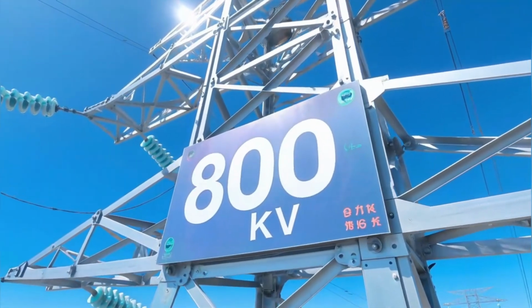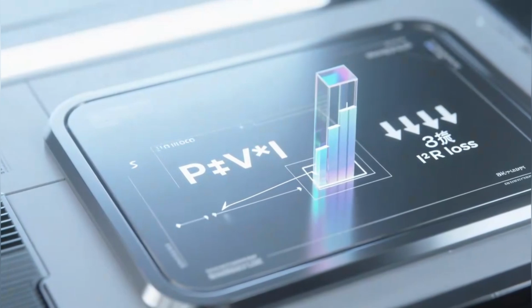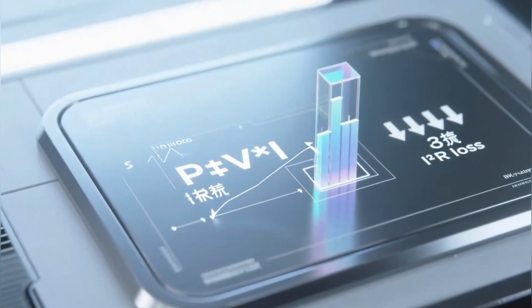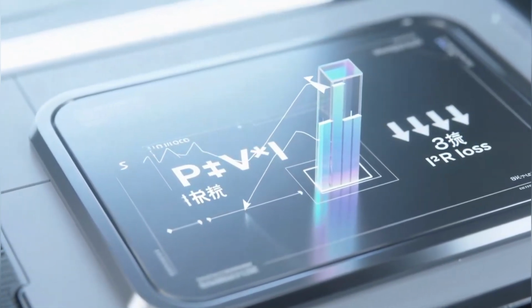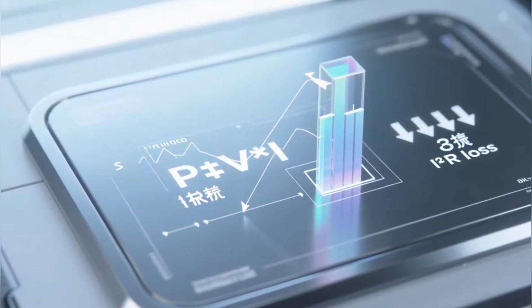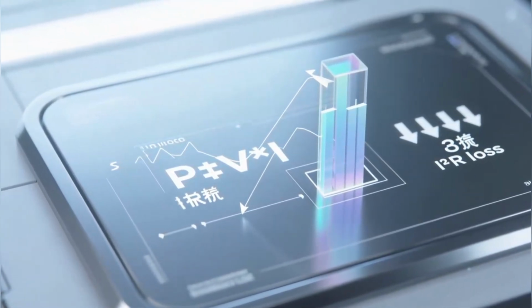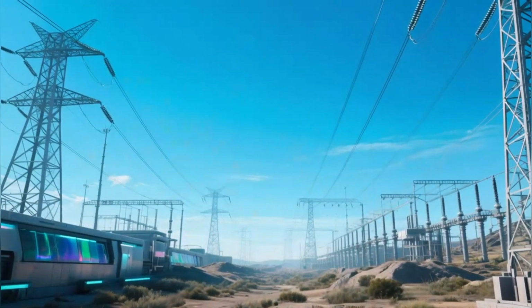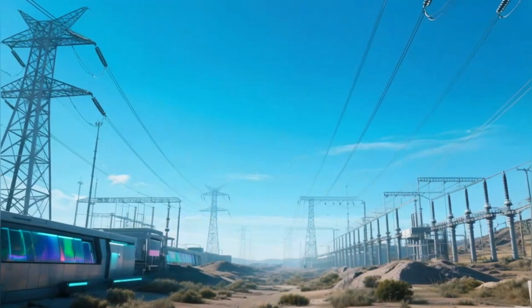Why is this important? Power transmitted in DC is P equals V times I. If we increase voltage, current decreases. I squared R losses decrease. Conductor size can be optimized. At plus 800 kV, the system can move enormous power with manageable losses.